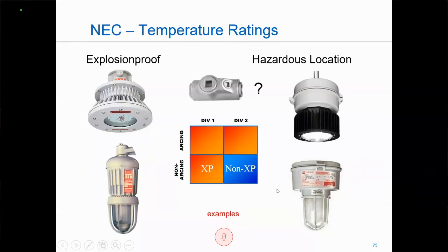So in this particular case, in my Class 1 Division 2, that's why this unit doesn't have to be explosion proof. It falls down here. So with this particular unit, Class 1 Division 2, I'm not required to seal that unit. It's not containing an explosion. It gets me no further integrity. When I'm in Class 1 Division 1, the answer is maybe. And here's why it's maybe.